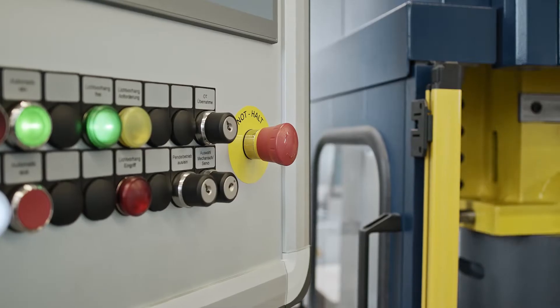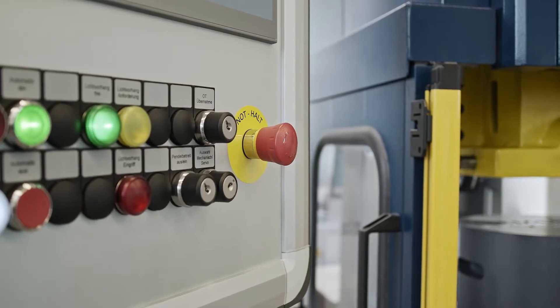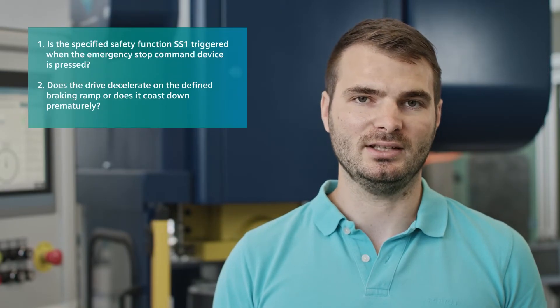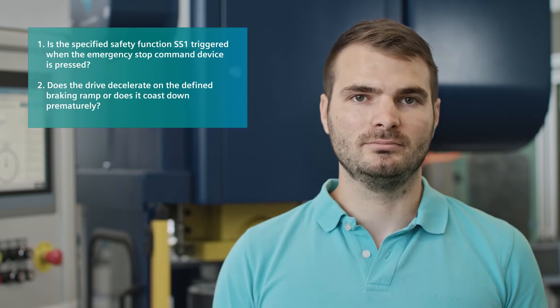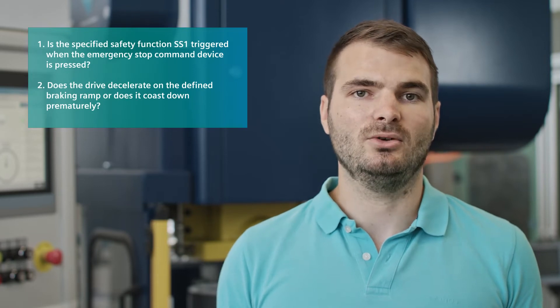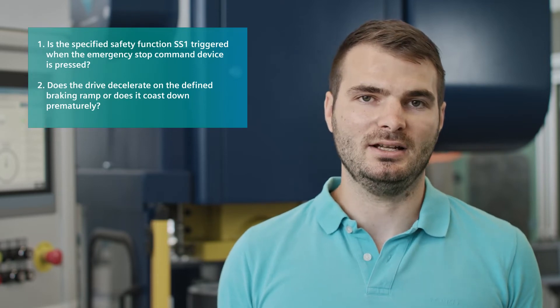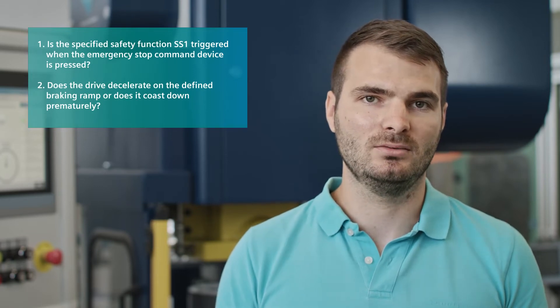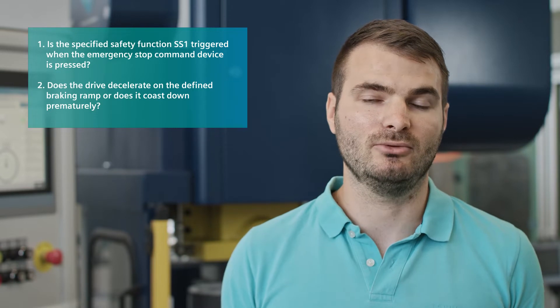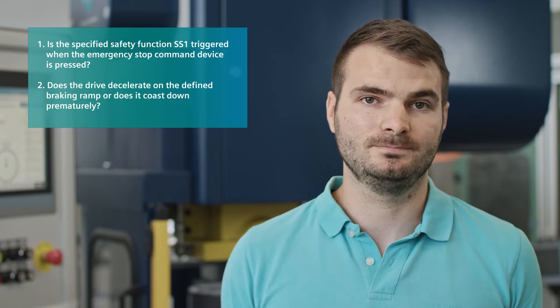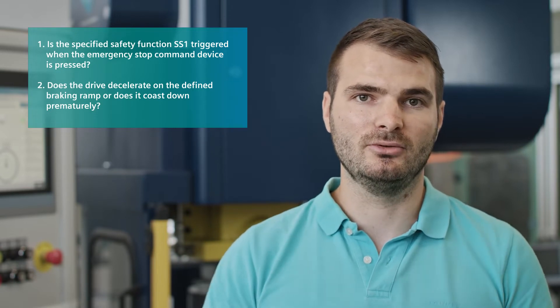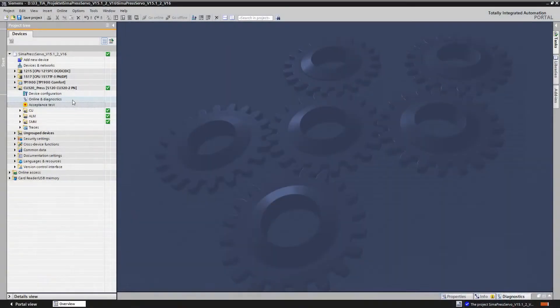Let's start first with the function of the emergency stop. Is the specified safety function SS1 actually triggered when the emergency stop command device is pressed? Does the drive really decelerate on the defined braking ramp or does it perhaps coast down prematurely? We don't know, and that's why we performed this function test and used the Start Drive acceptance test for this test and also for documenting the results.